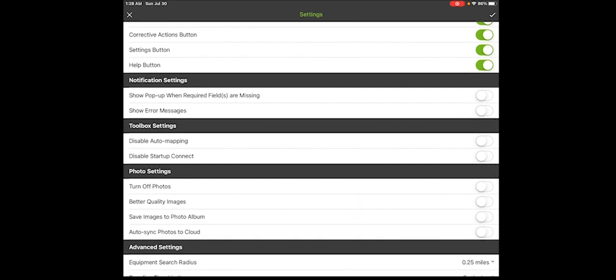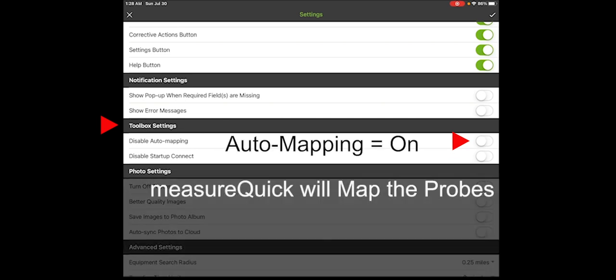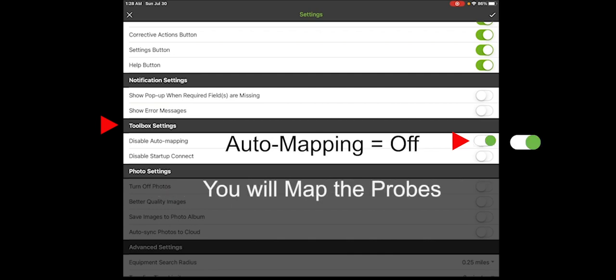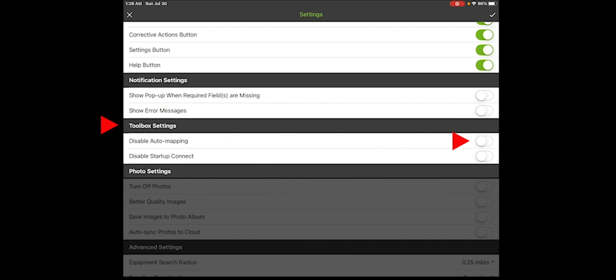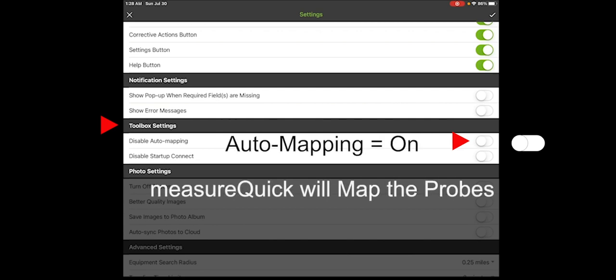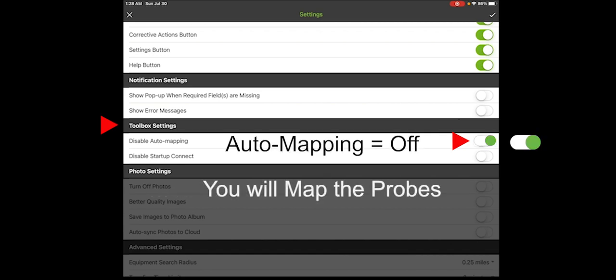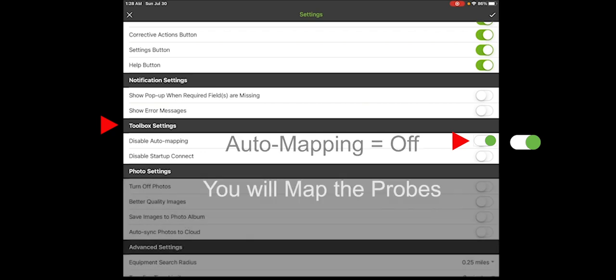The next is the toolbox settings. Let me explain what disable automapping is. So when you actually add a probe to MeasureQuick, you're going to map it to its use, whether it's a temperature probe and you decide if it's going to be the supply or the return or the outdoor air temperature. So when you have automapping disabled or off, then when you turn a probe on, MeasureQuick will automatically map it to the next available section. If you turn this on, then you are now enabling or disabling automapping. When you turn a probe on, you would have to physically map it to whatever it is you wanted it to read. If you're new to MeasureQuick or you're adding a bunch of probes to your application, the best thing you need to do is leave it in the off position and MeasureQuick will automatically map all of your probes as you turn them on. If you're adding just a few probes or changing some of the probes you've got, then you may want to activate this and disable automapping. And then you would map each one of the probes to what you wanted to read.